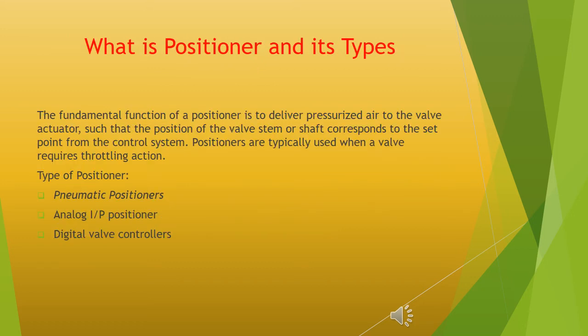What is a positioner and its types? The fundamental function of a positioner is to deliver pressurized air to the valve actuator such that the position of the valve stem or shaft corresponds to the set point from the control system. Positioners are typically used when a valve requires throttling action. Types of positioners: pneumatic positioners, analog I/P positioners, and digital valve controllers.